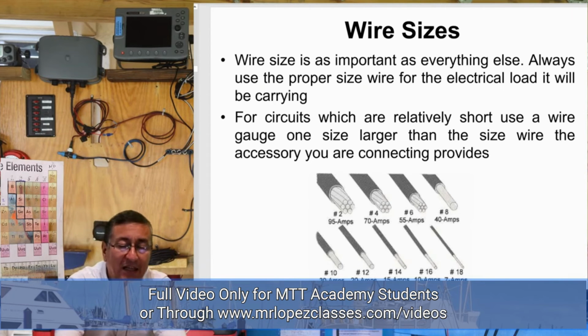This is important. For a gauge number 2, you can move 95 amps. For a gauge number 4, 70 amps. For a gauge number 6, 55 amps. For a gauge 16, only 10 amps. For a gauge 14, maximum 15 amps. For a gauge 12, maximum 20 amps. For a gauge 10, 30 amps.